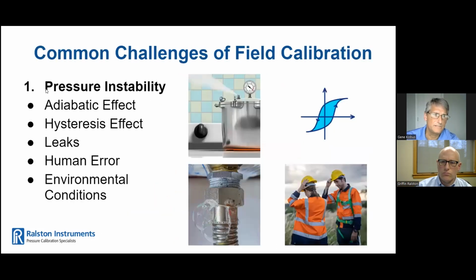Calibrating transmitters out in the field with a hydraulic hand pump definitely has its drawbacks. One of those drawbacks is pressure instability. Stable pressure generation is key to accuracy and consistency in pressure testing when you're using a hand pump, and there are lots of things that can affect stability.